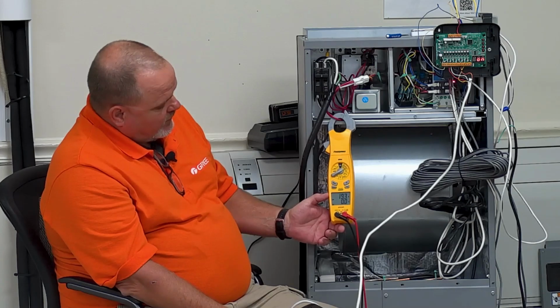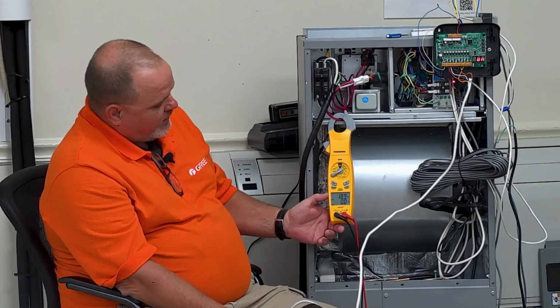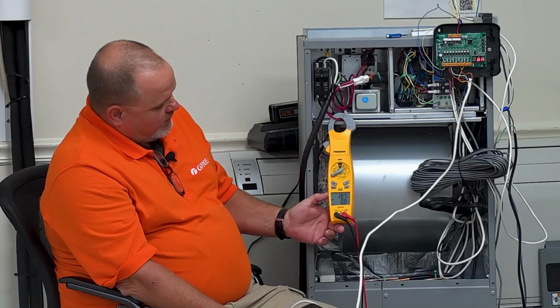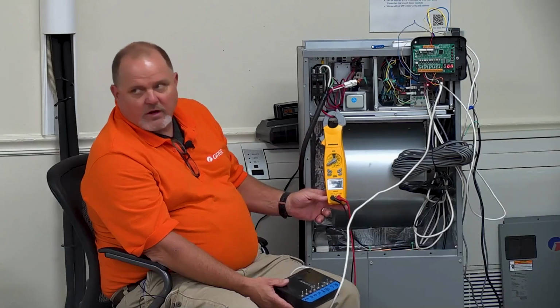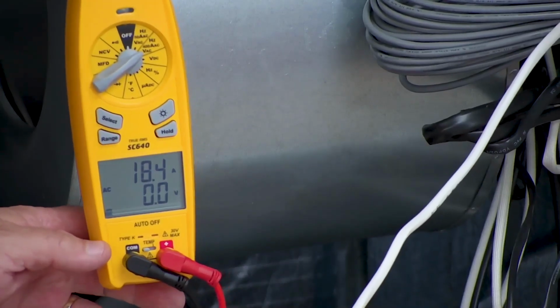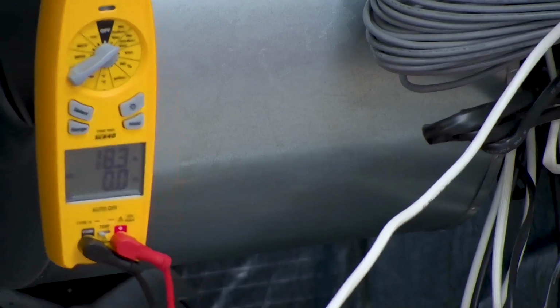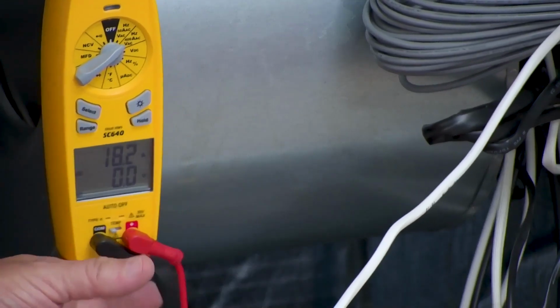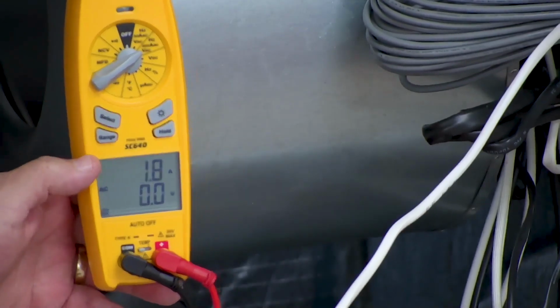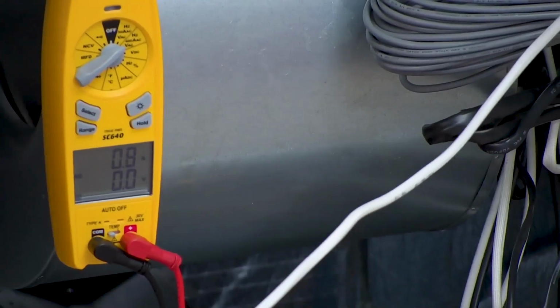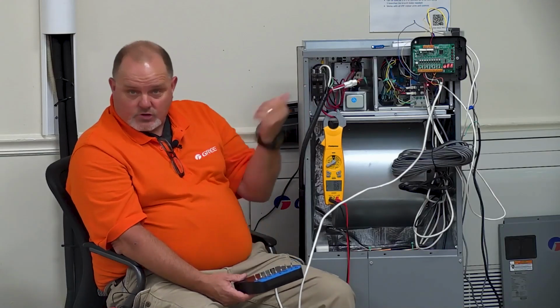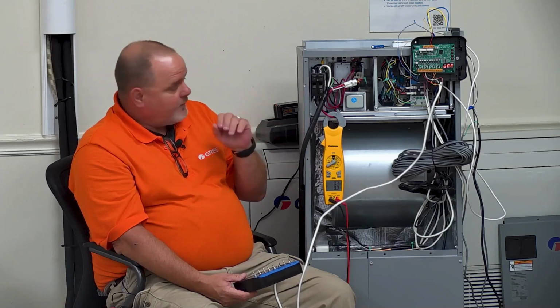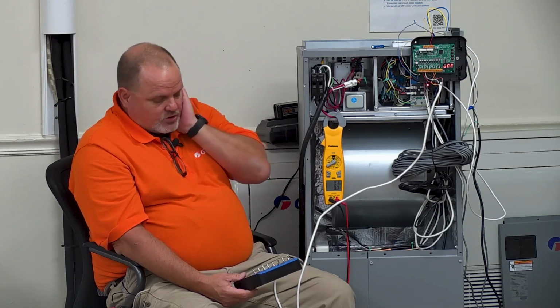There it goes. So I just got a little 5 kW heater in here, and it's pulling like 18.6 amps. It's 208 voltage, so it absolutely functions. So now when I lose that heat call, I'm going to lose that electric heat call, but that blower's got a delay in it. Regardless of the delay, as you seen when I did the G call, I didn't have a blower off at all. But now that I gave electric heat call, it does give me a blower off. So it'll take a minute for it to shut down.